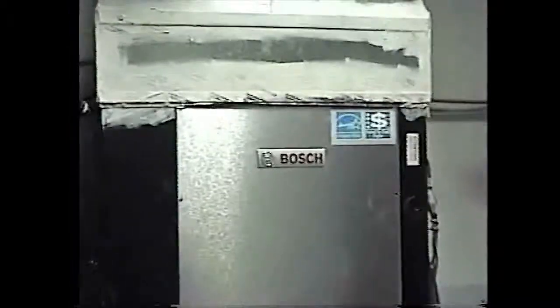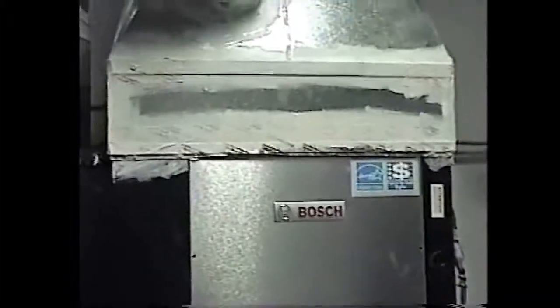Okay, now the sound of the compressor's gone, thermostat satisfied. Now we're going to run out the residual heat in the system. As you can tell, the pitch has not changed on the fan motor at all. Just because I shut the machine down doesn't mean I gotta stop shoveling heat. There we go. You can just hear it start to back off. You've heard the same sound at altitude when they're flying in a jet airplane. They back off of the engines when they're ready for descent. This is doing exactly the same thing. And we're back to just about idle speed, and we're stirring. Now we're going to stir the air until there's another call for heating.